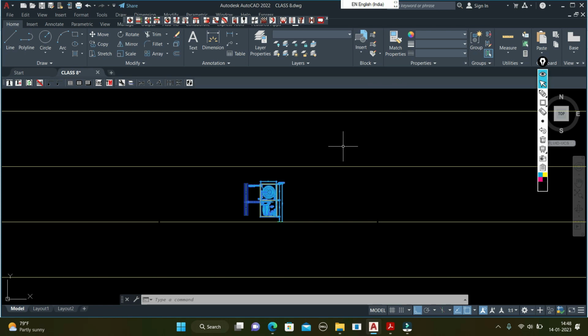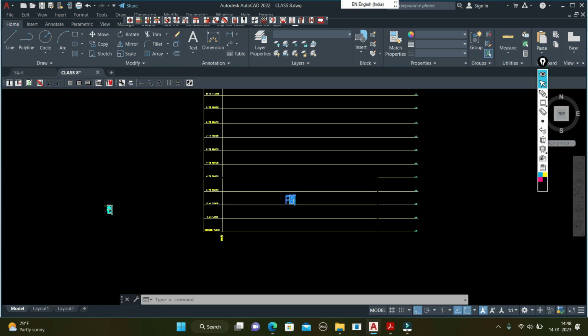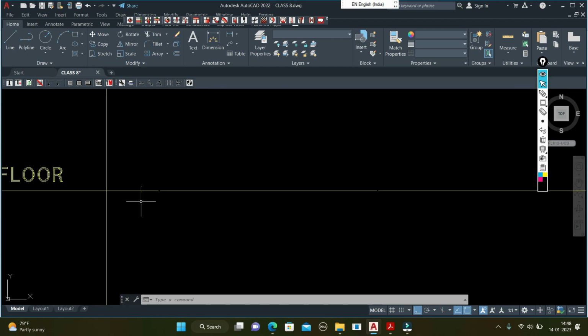In light hazard it is 52,000 square feet. If that floor exceeds 52,000 square feet, then we take two risers. All these hazards have different zone limitations, so kindly watch my previous video.